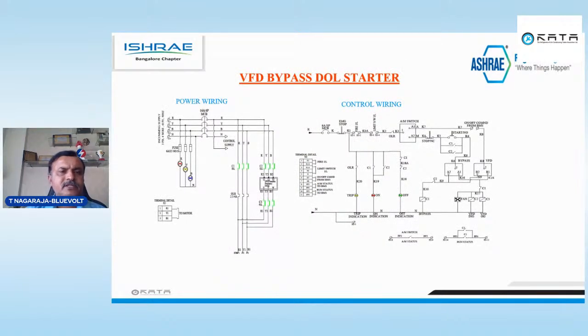This is a VFD bypass DOL starter. See, this is the one incomer, then fuses for the indication lamps, and the bypass contactor. See here what I told, the VFD drive input and output both get isolated. Suppose it is running in bypass mode, supply will go through the overload protection and the motor will run, but voltage will not go to the VFD. In the same way, whenever it is switched off, this contactor also will be off and your drive will be safe.